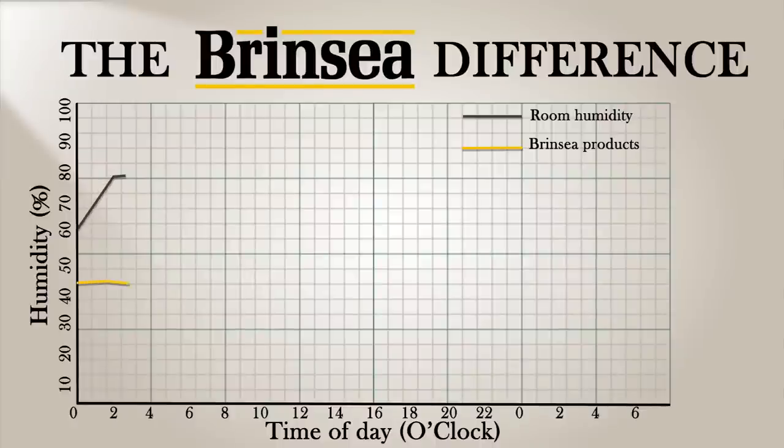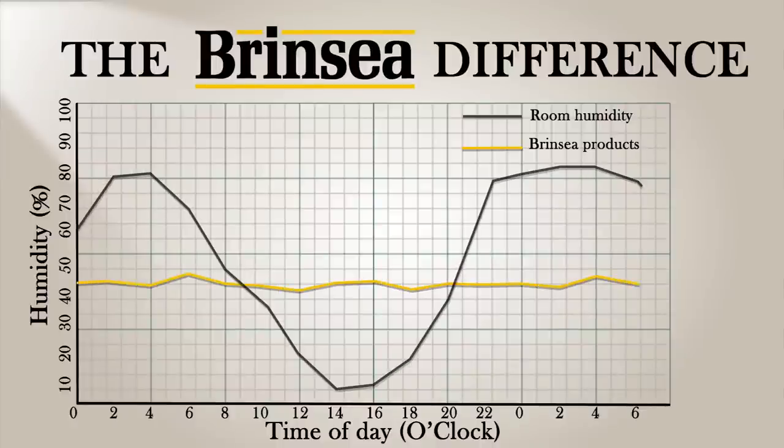All our standard OvaEasy Advanced Series 2 models provide a continuous readout of incubation humidity so that you can achieve the ideal level. Our EX version has a separate pump to maintain a precise level no matter what the humidity in the room. The humidity pump includes an external water reservoir which removes the chances of water in the incubator harbouring bacteria.